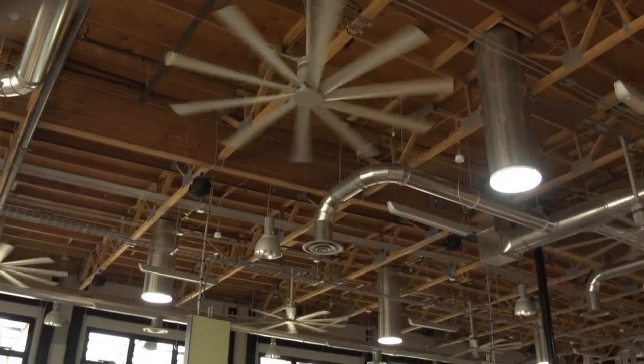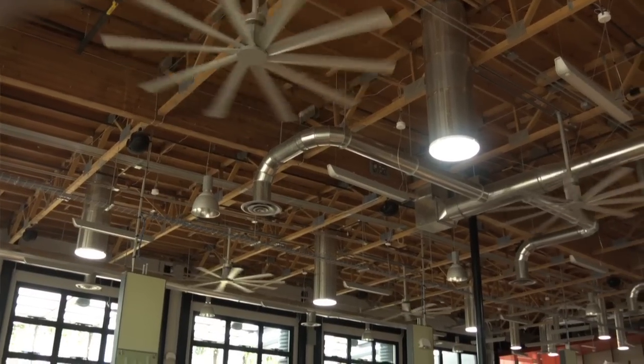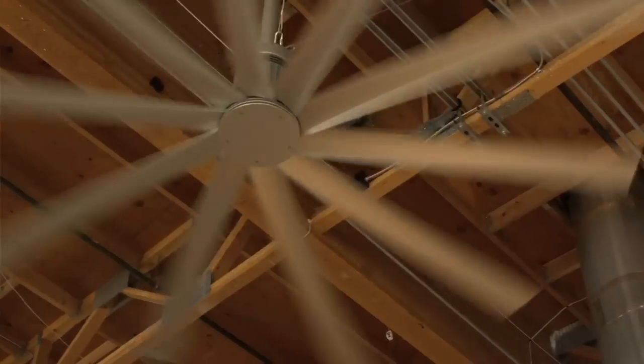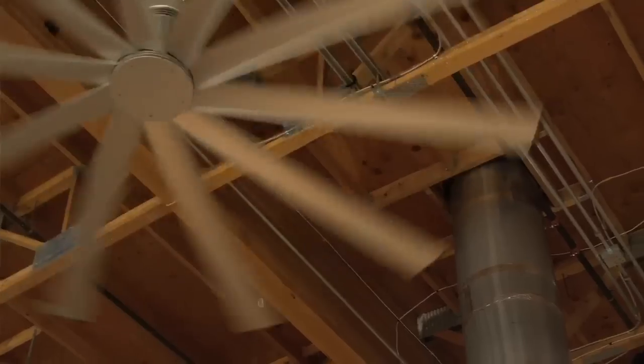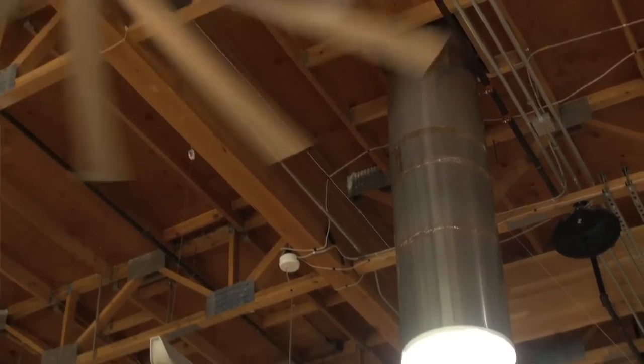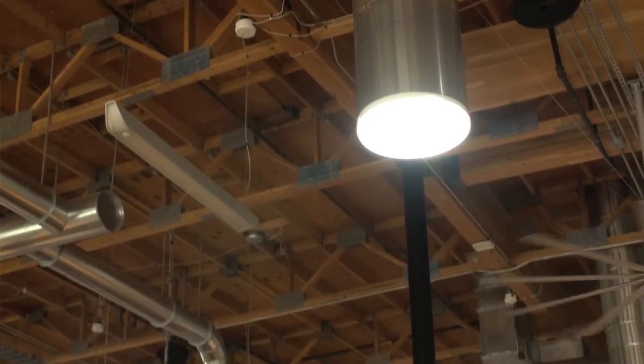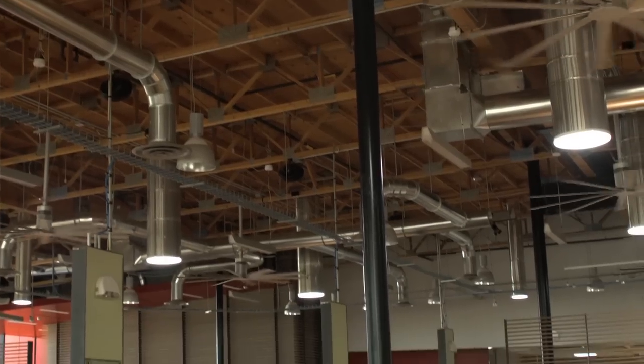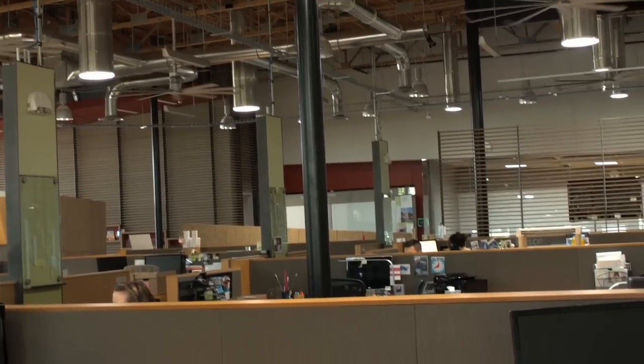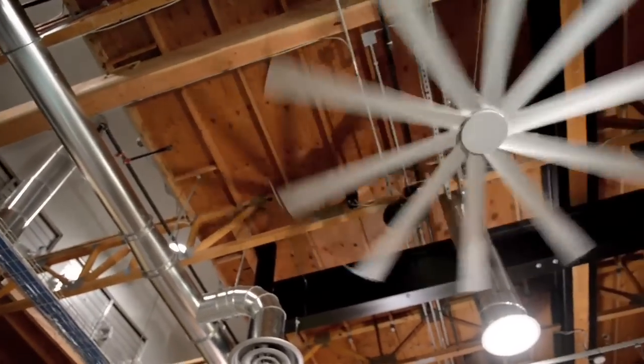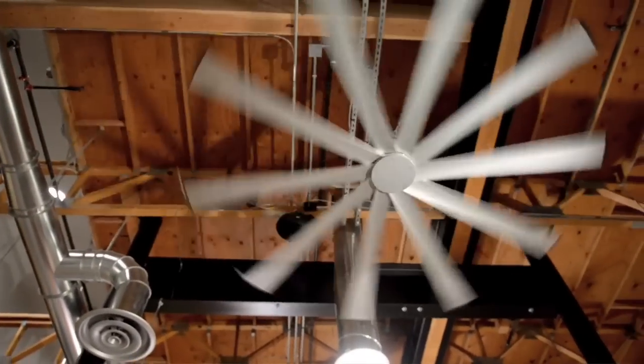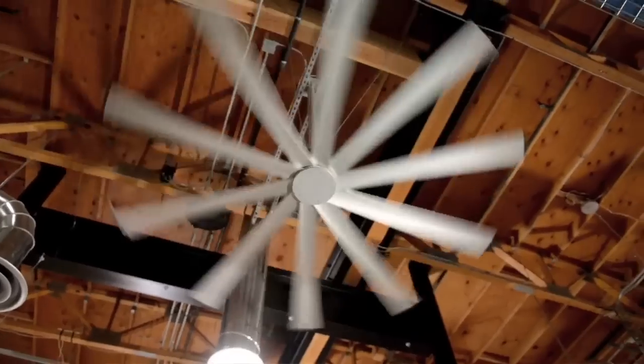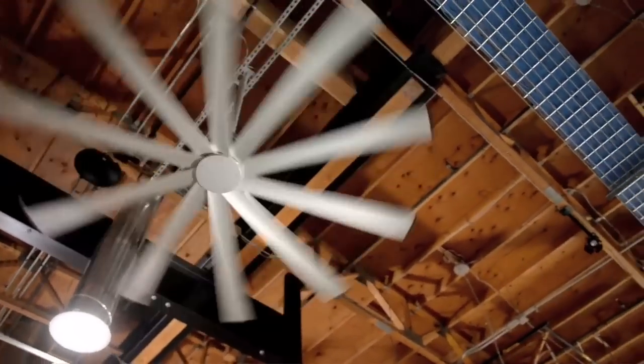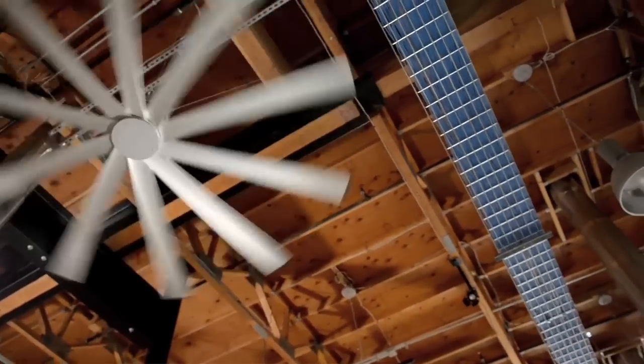We modelled those fans by increasing the velocity of the air in the space. The impact was that we limited the stratification and mixed the air. It was our original concept that we wouldn't do that, and I originally recommended against it. However, after modelling and now after a year of occupancy, there is no doubt that adding the fans and mixing the air is a far better addition to thermal comfort than stratifying it.